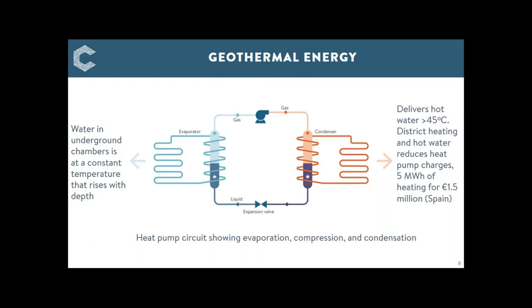One project I looked at is near a colliery in Spain that has water at a constant temperature of 23 centigrade. In this case, the water had to be pumped out anyway, so the extra costs are in distribution of the heated circuit and the heat pump installation, which costs around €1.5 million. The system provides about 5 megawatts of heat, enough for a local hospital and other key buildings.